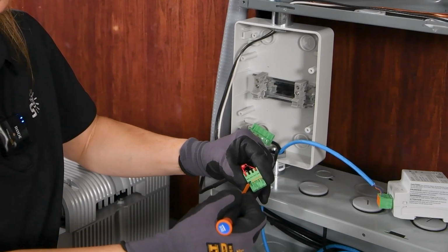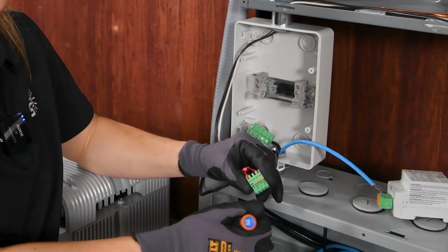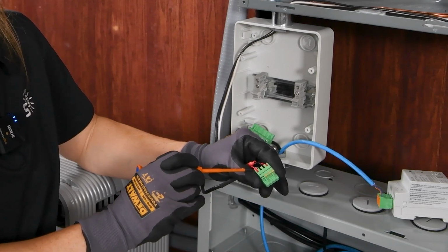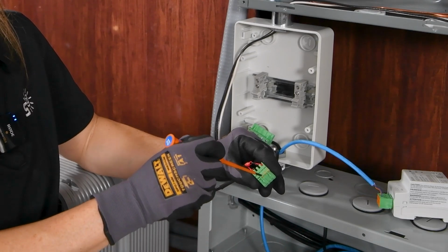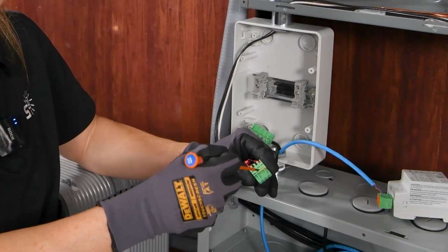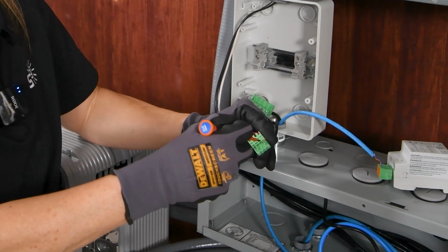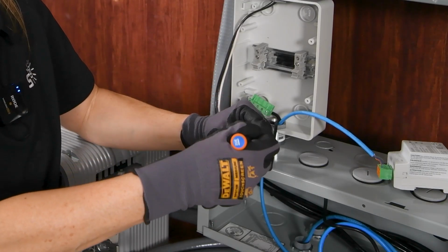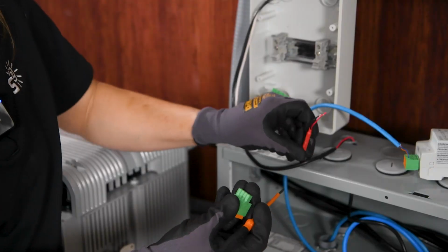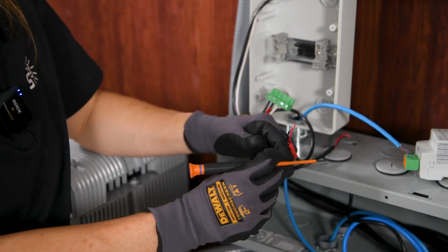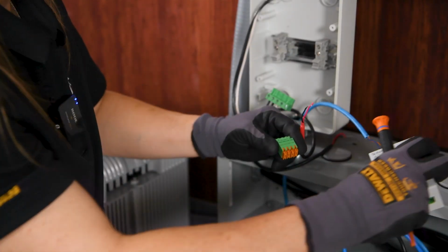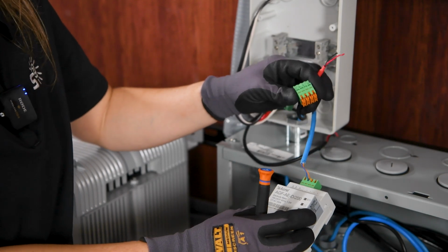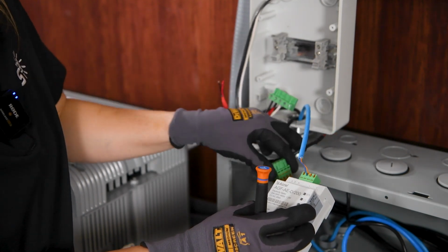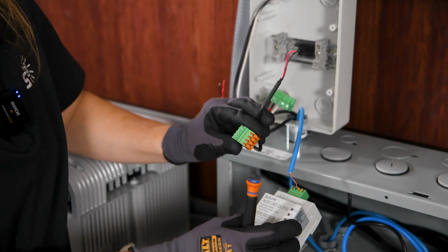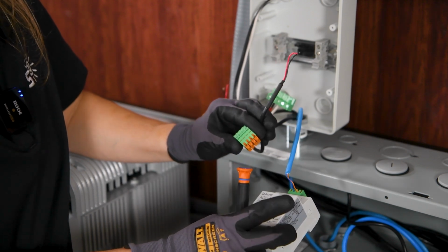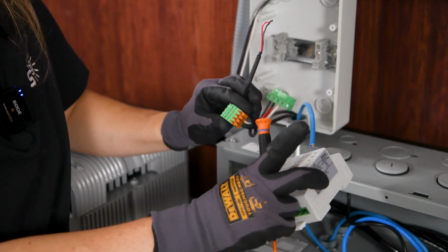and move your screwdriver in the upward position, and that will move your pin up. We'll do that for all 4 of these connectors so that these wire terminals will be exposed and these wires can be removed. Now, one thing you'll want to be sure of as you reconnect these and insert your 4-pin connector is that your red will be your L2 and your black will be your L1 so that we stay consistent with everything that we've connected so far down the line.